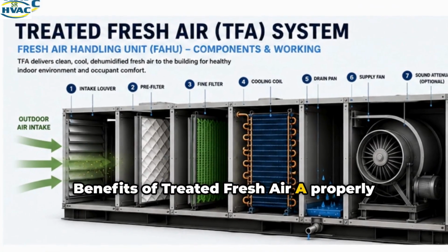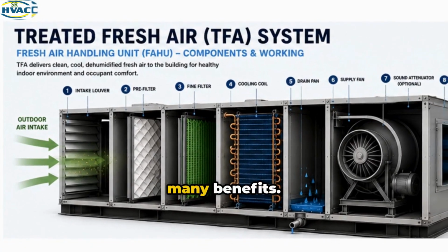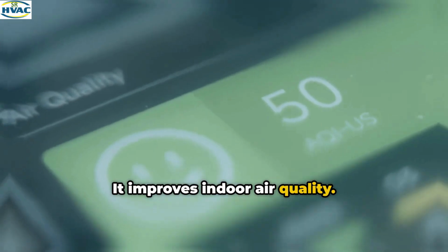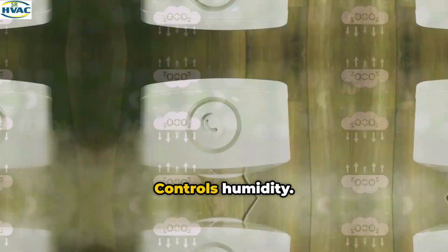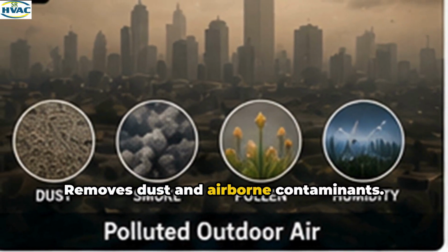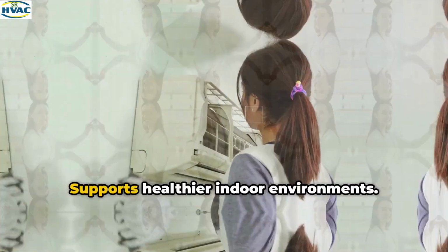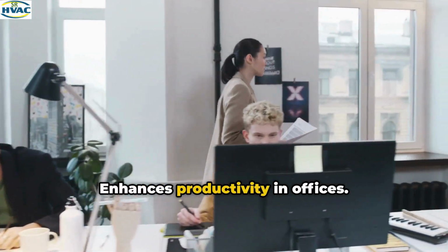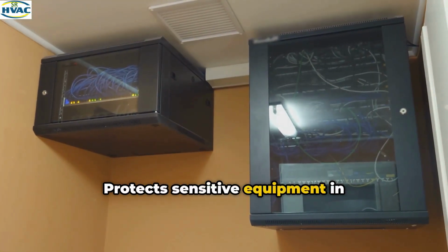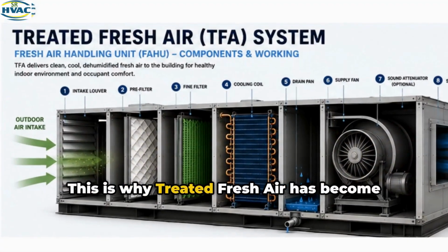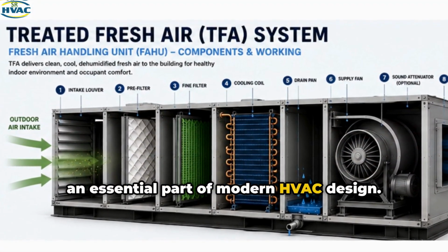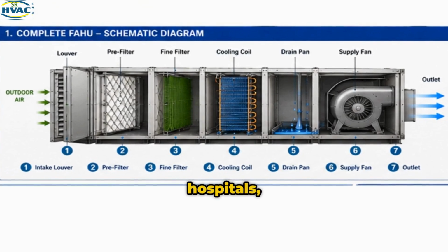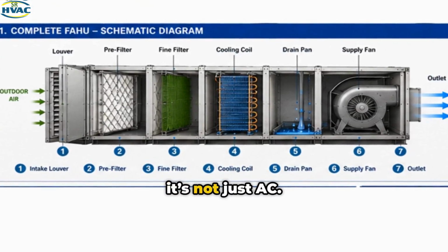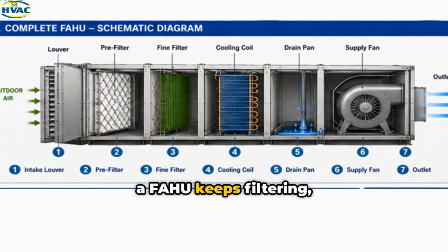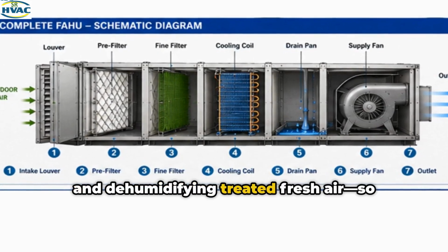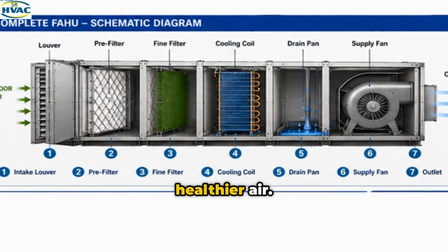Benefits of treated fresh air. A properly designed treated fresh air system provides many benefits. It improves indoor air quality, reduces carbon dioxide concentration, controls humidity, removes dust and airborne contaminants, improves occupant comfort, supports healthier indoor environments, enhances productivity in offices, protects sensitive equipment in specialized facilities. This is why treated fresh air has become an essential part of modern HVAC design. In malls, hospitals, airports, hotels, and offices, it's not just AC. Behind the scenes, a FAHU keeps filtering, cooling, and dehumidifying treated fresh air so everyone breathes cleaner, healthier air.